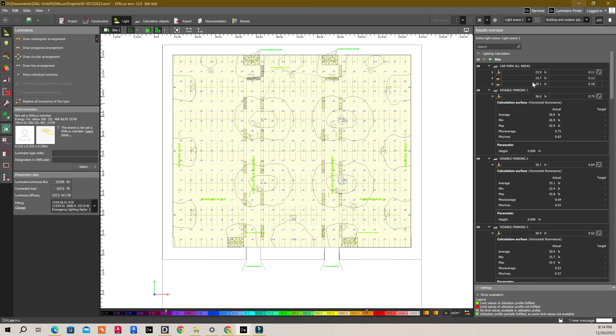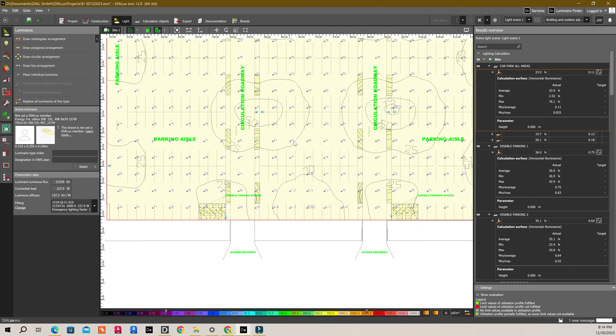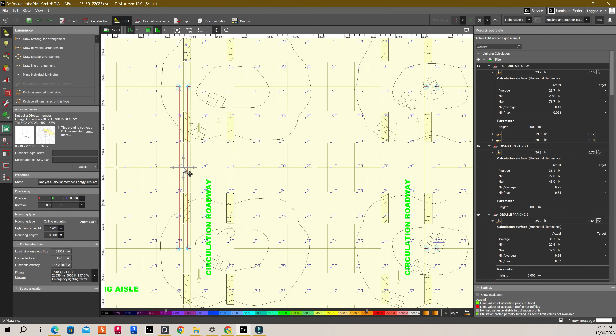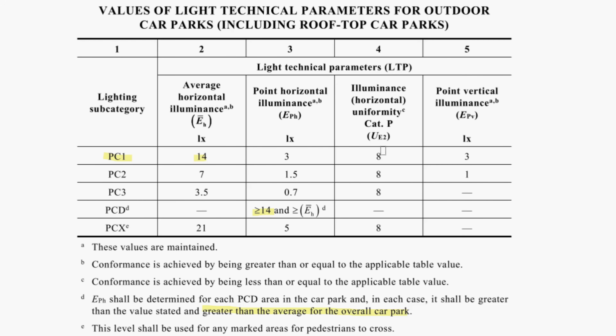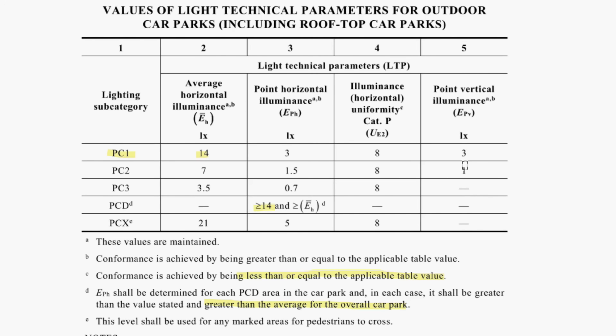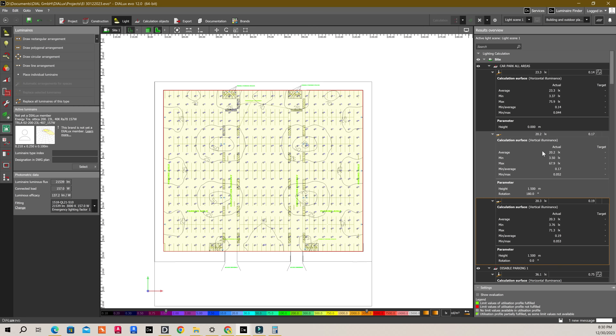Let's rerun the calculations and see the results. Checking the lux levels for the overall car park — the horizontal average is 14 which is fine — but the minimum point horizontal lux is below 3. So let's move these 2 poles from the center area to the left side and see if we can get the horizontal point lux to greater than 3. After doing this and re-running the calculation, the minimum point is 3.4. As discussed in part 1, the illuminance uniformity value should not be greater than 8. Dividing 75 by 23 gives us a value of 3.2, which is compliant. For point vertical illuminance, the minimum value required is 3, and both of our vertical calculation surface point vertical values are greater than 3. So we are complying with the standard.